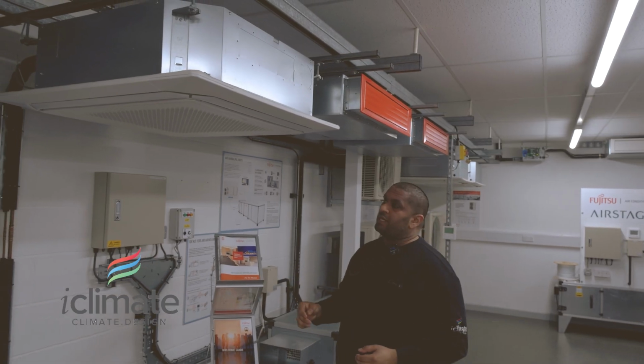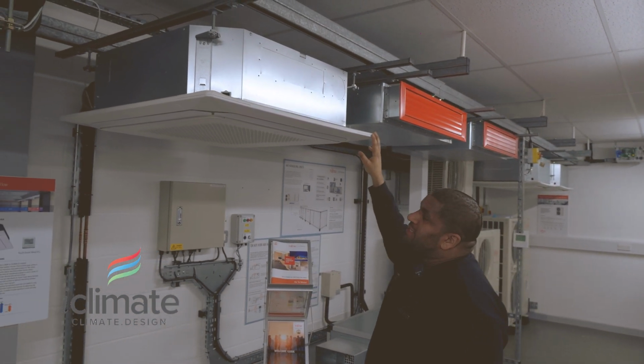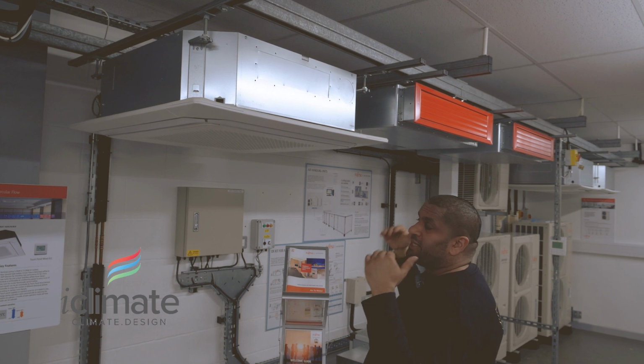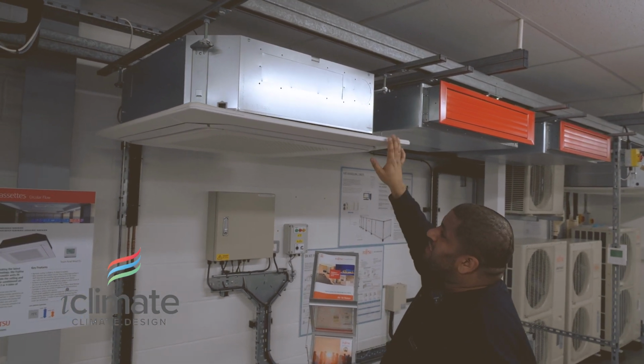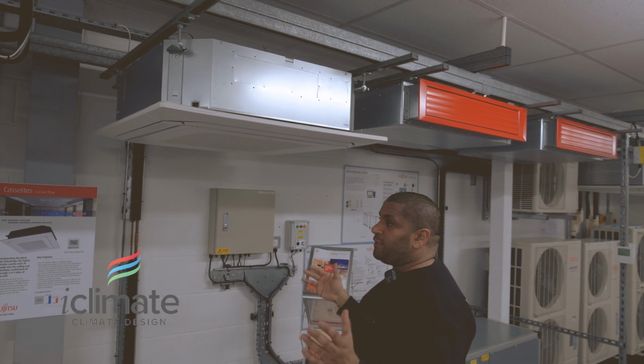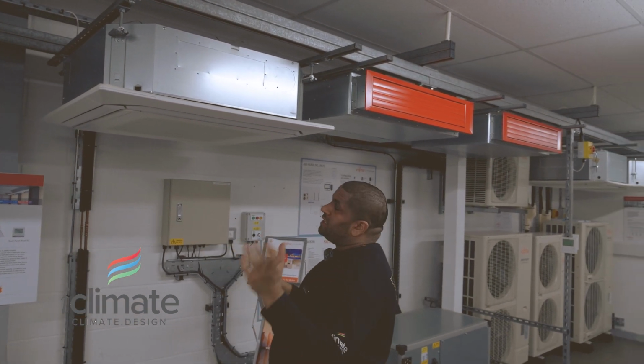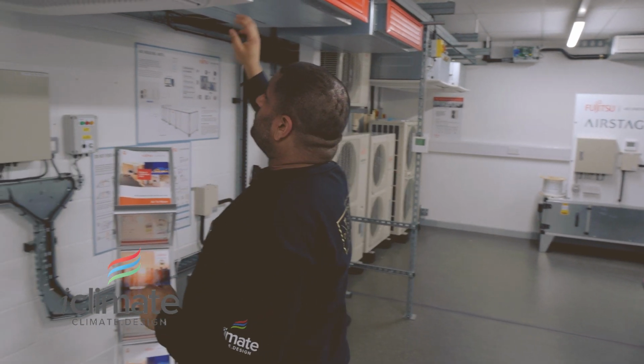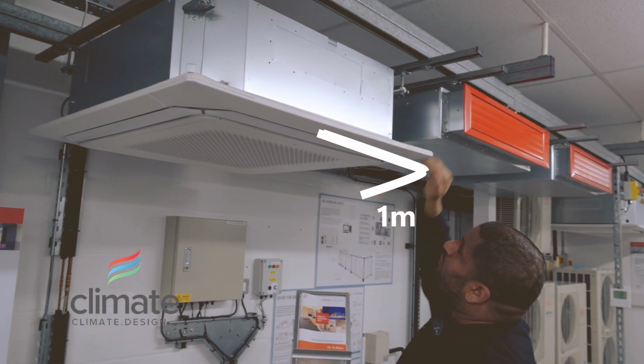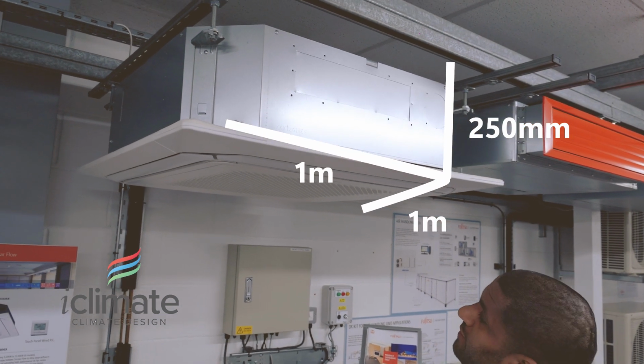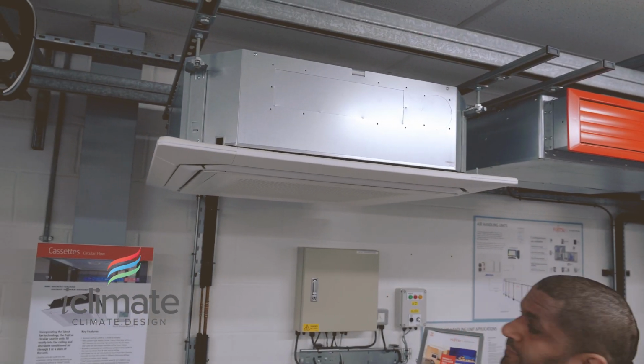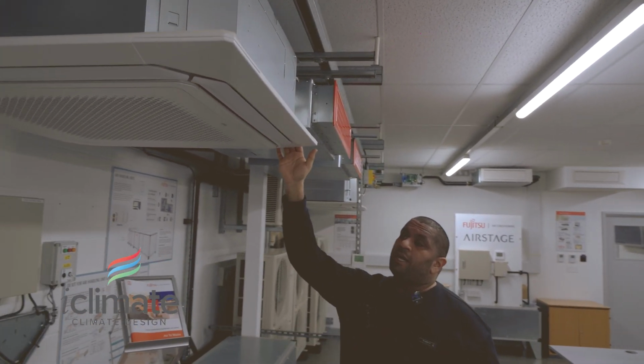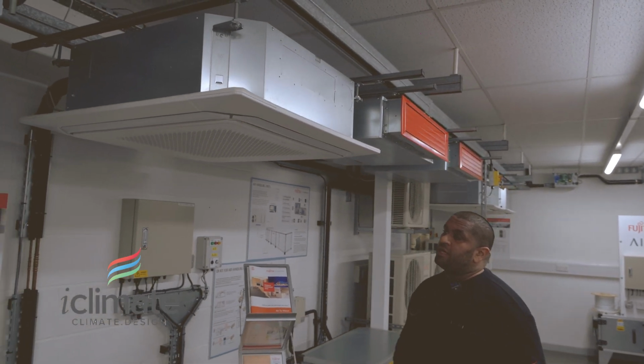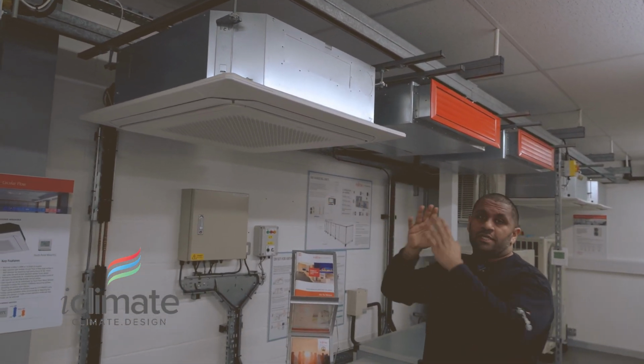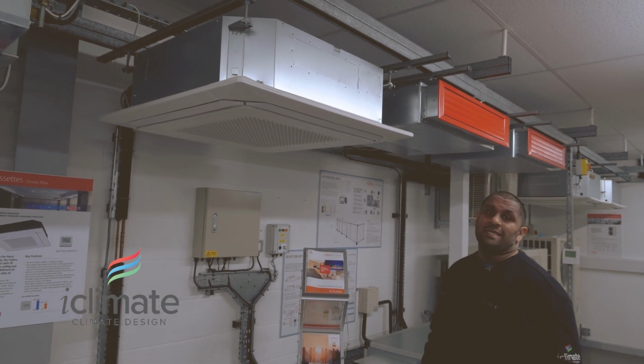The next type of unit is what we call a ceiling cassette type of unit, which is here. It's essentially a square that sits within a suspended ceiling or a bulkhead ceiling. The difference with this is if you don't have the space within your ceiling configuration to run ductwork through to hide the air conditioner and the outlets. The dimensions of this indoor unit is approximately 1 meter by 1 meter, and you would need a ceiling height of 250 millimeters to suspend this up into your ceiling. This is ideal if you don't have space within the bulkhead and too many obstacles, and you wish to supply your office or commercial space with conditioned air at a very even stratified output. This is the unit you need, a ceiling cassette.